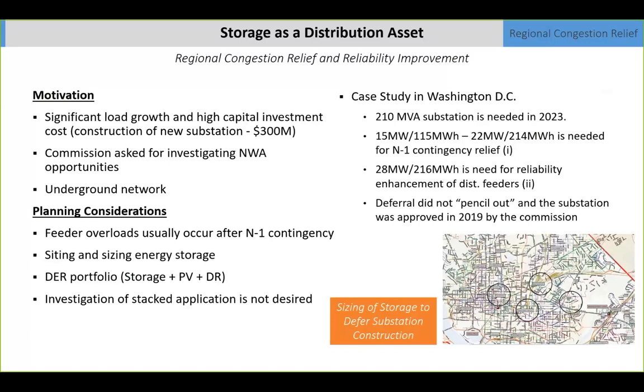In other words, parking garages were being replaced with high-tech office buildings, so the load would go up, and the 6 feeders serving the network wouldn't be able to carry it when only 5 were in service, which is the reliability standard for the underground network. Stakeholders argued you could avoid building that station by putting batteries in the network. Thousands of hours of analysis went into simulating the network, the feeders, the station, and the batteries - looking at how big the batteries had to be, how they would be operated, and what the economics were. And the economics were strongly against using batteries in this case.